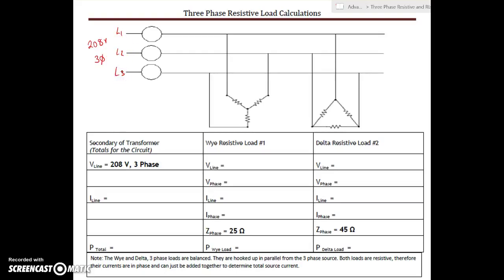No neutral required here because we have balanced loads. Each of these guys is 25 ohms, and each of these loads on the delta are going to be 45 ohms. They're all being fed from 208, so we have 208 volts as the line voltage.